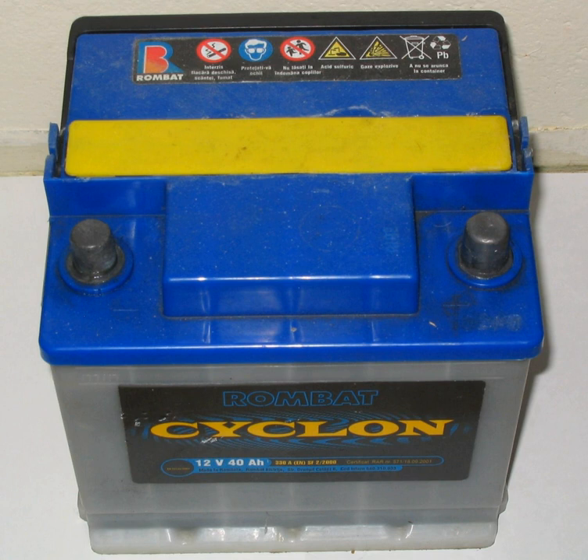The battery's open-circuit voltage can also be used to gauge the state of charge. If the connections to the individual cells are accessible, the state of charge of each cell can be determined, which can provide a guide as to the state of health of the battery as a whole; otherwise the overall battery voltage may be assessed.